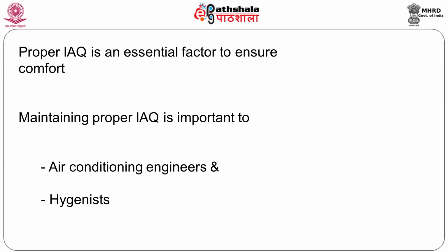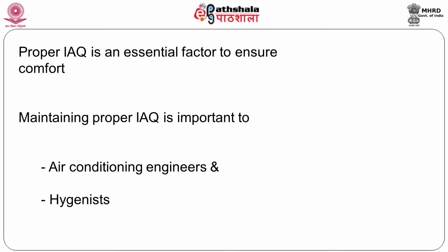So I want to dilute the odor. I want to dilute that pollution caused by the odor. What do I do? I put in 5 CFM extra so that the air will feel a little more fresh. So in other words, I have diluted to get rid of pollution. Now as I mentioned, the two breeds of people who are very interested in this field of air quantity for ventilation are the air conditioning man, obviously because it affects his heat load, and the hygienist who is worried about your health. You have a proper air quantity, you get proper factors for air.